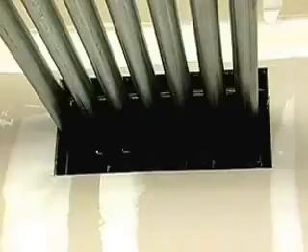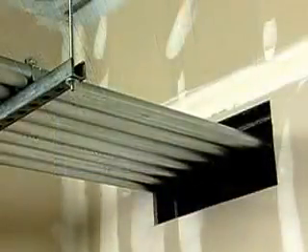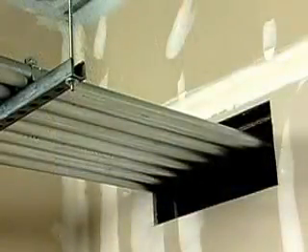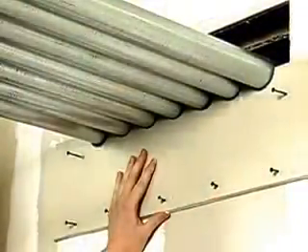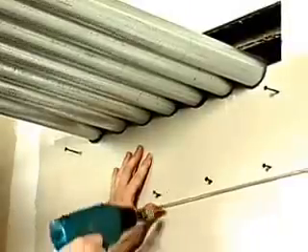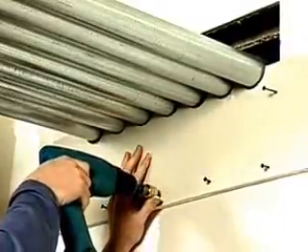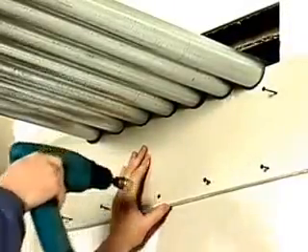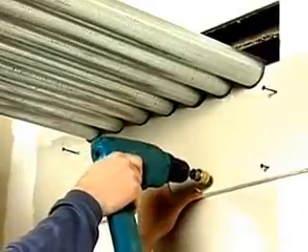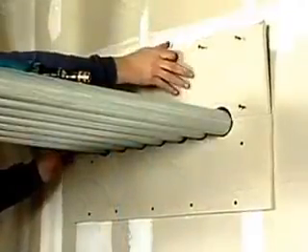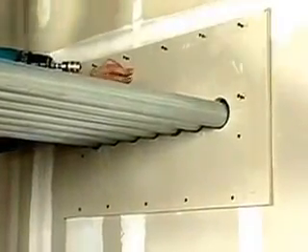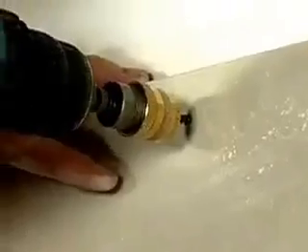These openings are often designed with future capacity in mind and are frequently far larger than immediately necessary. Excessively large openings can complicate fire stopping and may require a reduction of the opening size before the fire stop itself can be addressed. Sometimes this is simply a matter of scabbing down a hole using layers of fire-rated gypsum wallboard or forming a dam and pouring Firestop mortar into the opening.